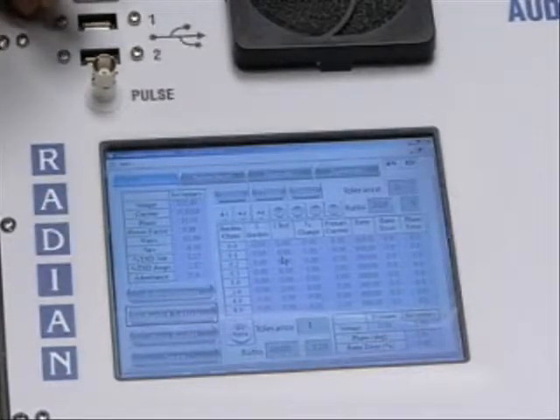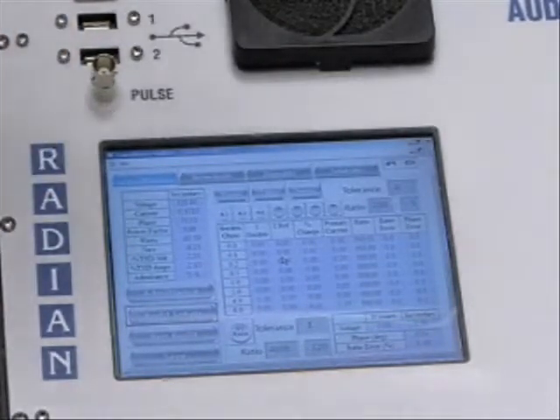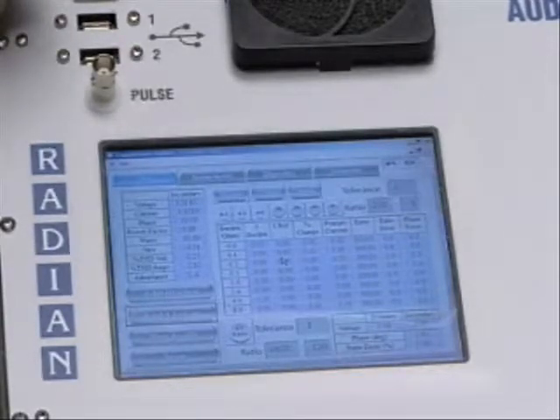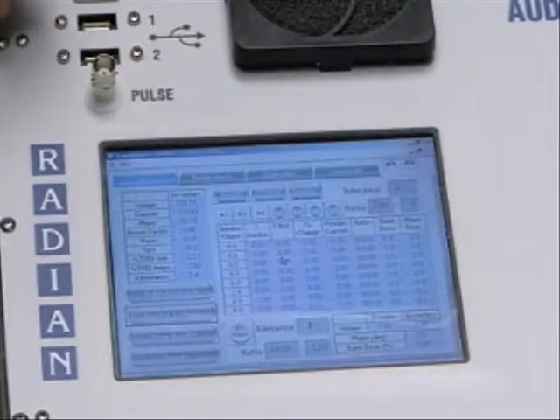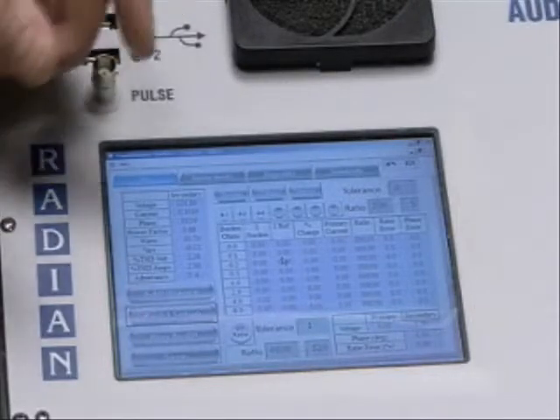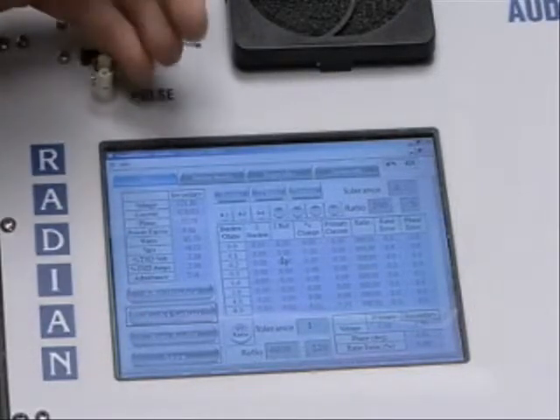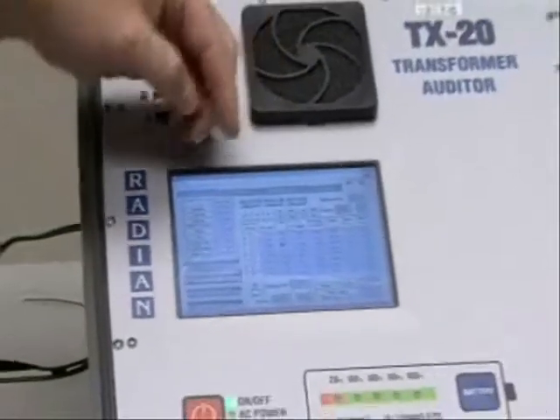So in order to do a burden test, I'm going to first look at the CT and make sure I know what the burden rating of that CT is. This particular CT is rated at 0.5 ohms. I like to perform a burden test up to the rated burden plus 1 past it.